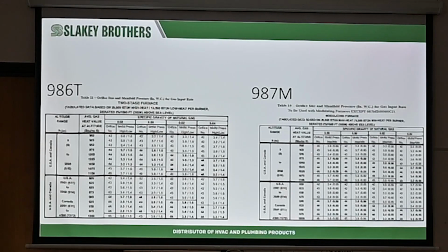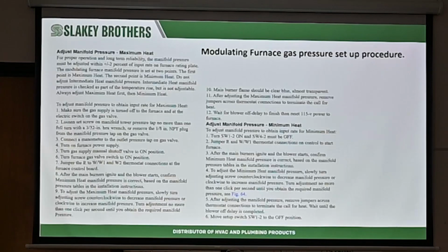And for you guys, you can see, now I think this is for all of them. This isn't just like a BTU rating. This is for all the furnaces. 3.3, 3.5 for the high, but 0.55 for the low. Okay? And same thing over here on the two-stage. Turn it on. You could try the lower rating, the 1.4, and you might be good there, or even 1.5, and you'll probably be okay there. But definitely on the 987M, follow their little procedure, and you'll get used to it.